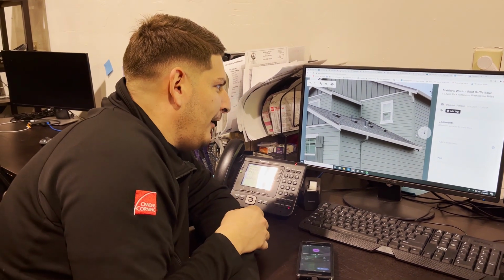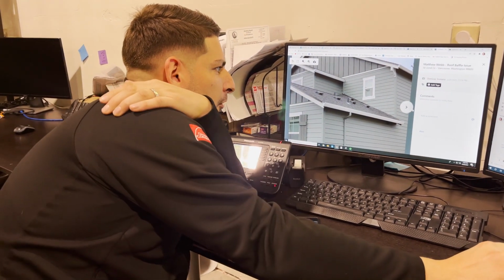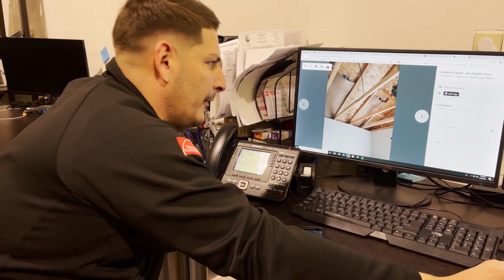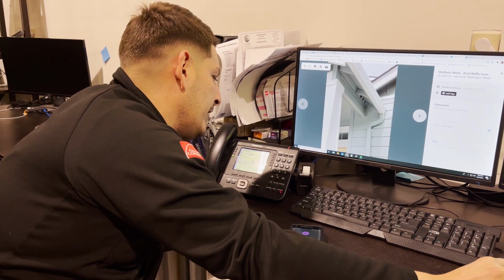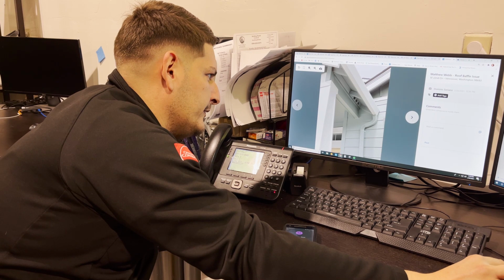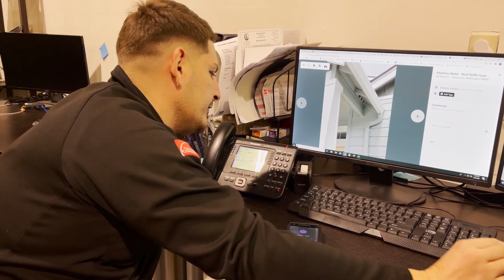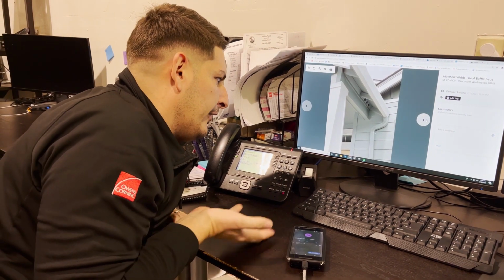But I'm here with Dominic, and I'm looking at your situation you have here, right? And so I was talking with Dominic, and he was basically like, why, you know, these vents that you have down there on the intake. I hate to say it, but they're exhaust vents, right? So they're not made for intake. They work as intake, like air goes inside of them, but they're made for air to come out, which is why you're leaking.